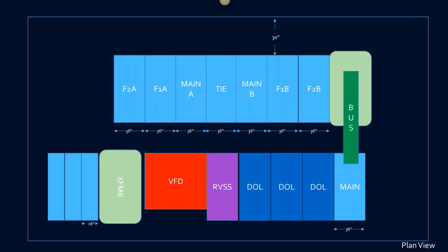And this is what that does for us, especially in applications where the client is dead set on UL 1558 gear. It's going to be very, very deep anyway. Turn the transformer 90 degrees and you will save quite a bit of linear width, because then the transformer will be about as deep as the UL 1558 gear.